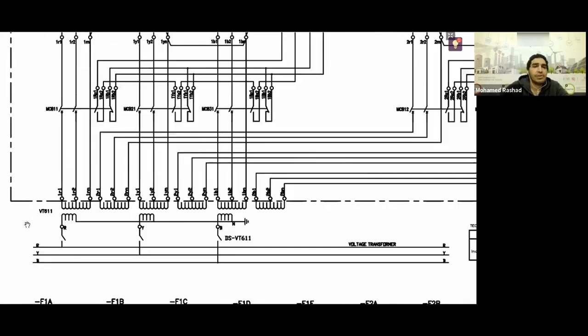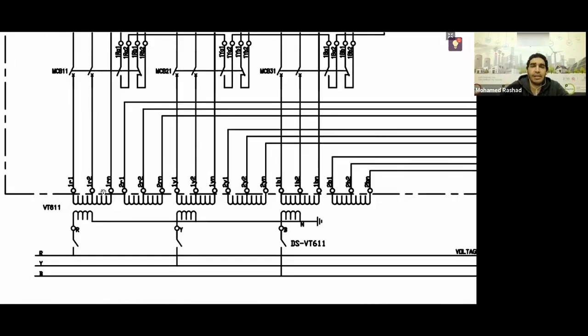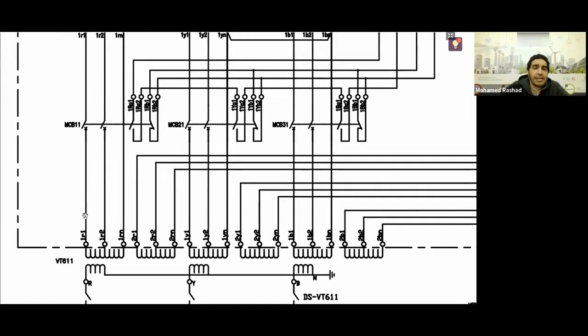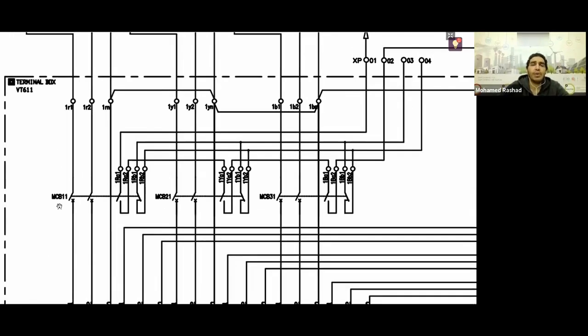So what are these? Look, now isn't this the second winding? Come, you'll find this second winding. Isn't it here like this and cut off by an MCB, or their wires are connected through an MCB? If this miniature circuit breaker, guys, is closed, then this contact is closed. We always said the miniature circuit breaker is drawn and its normal position is what? Open. So its contact drawn here is normally open when the MCB is open. Naturally, you close this MCB to supply power to your control and protection circuits. So this contact should also close.